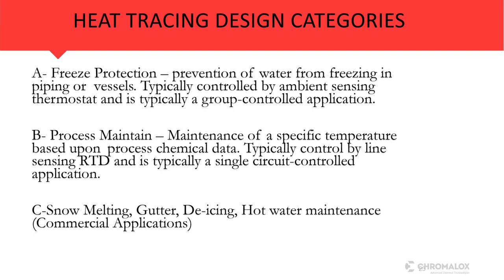To me, there are three different design categories. There's what we call freeze protection, and freeze protection is the prevention of water from freezing in pipes and vessels. That's typically controlled by an ambient sensing thermostat and is a group controlled application. Most people are probably aware that I'm turning on a number of circuits with a contactor when I get below a certain temperature, and then when I get above a certain temperature I turn those off. So that's what we typically refer to as freeze protection. We're typically dealing with water.